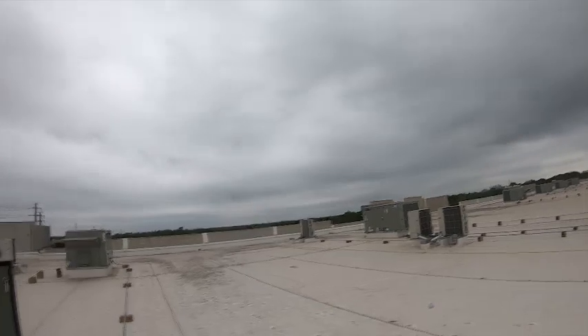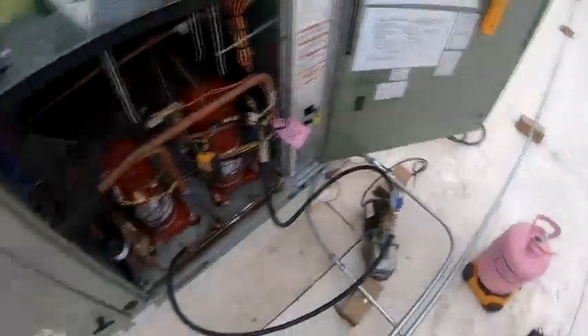All right. See, I'm trying to beat this weather coming in. I feel some sprinkles. We got it down to about 547. See, we need 6.2 pounds. Like I say, I'm going to feed it directly in the hoses right here, so I'm going to add a little bit more than 6.2 to make up for the refrigerant that's in the hoses. Let's say 6.2. I'm going to isolate the vacuum pump right here. Also, we're just going to make sure that it doesn't go above 1,000. Like I say, this is going to guarantee that I don't have any leaks or moisture in the system.